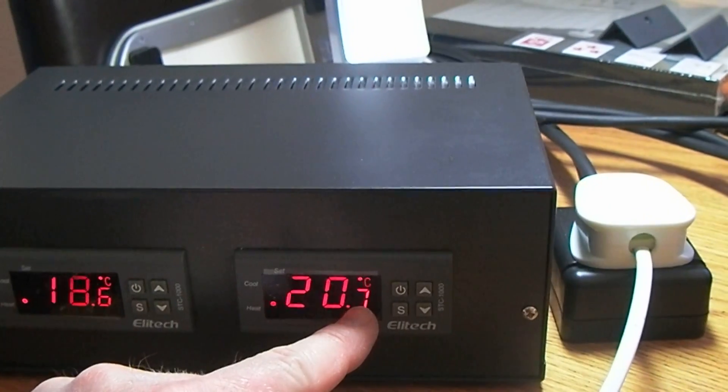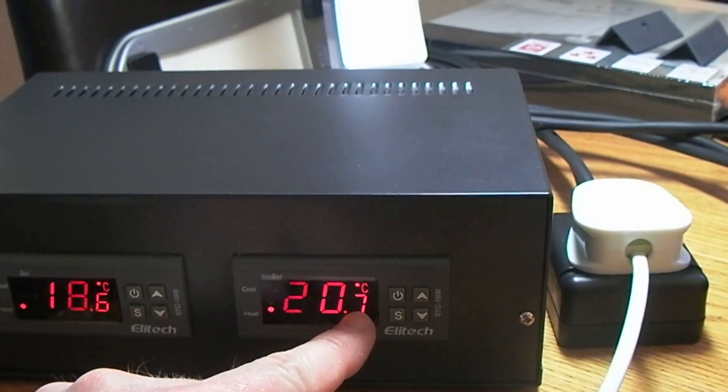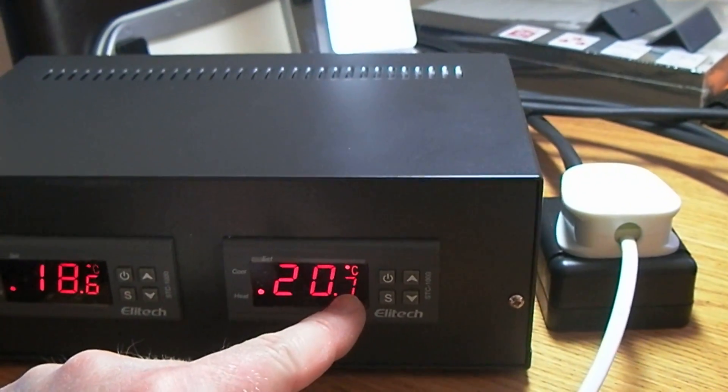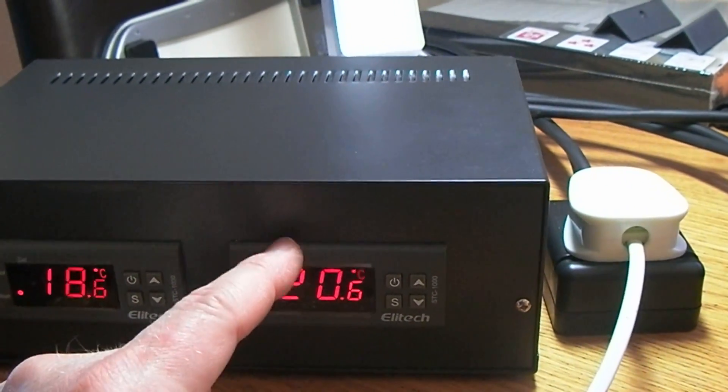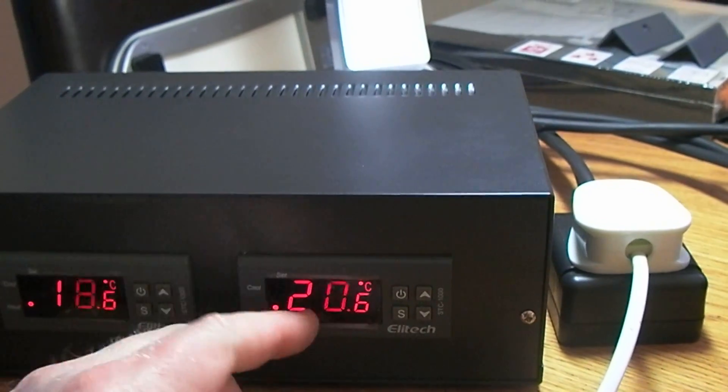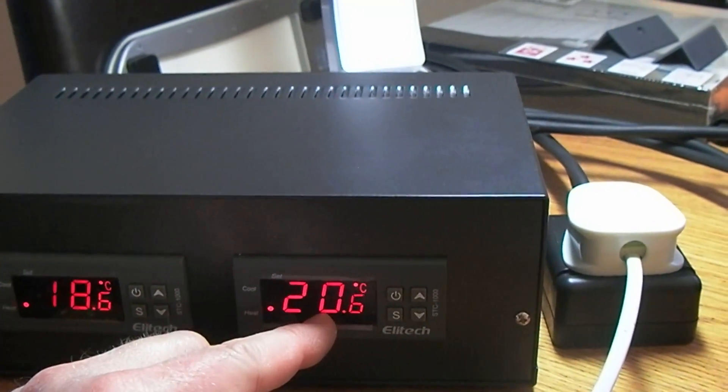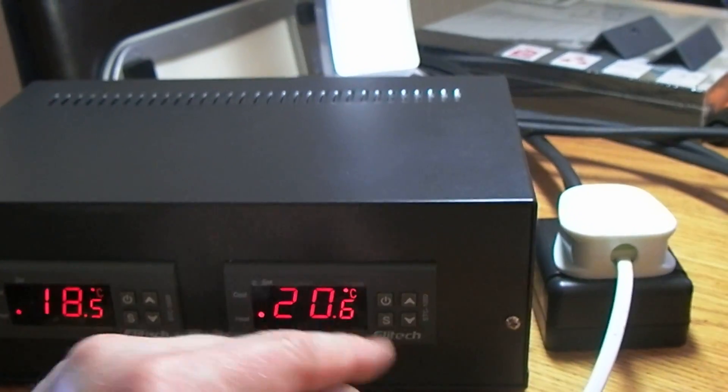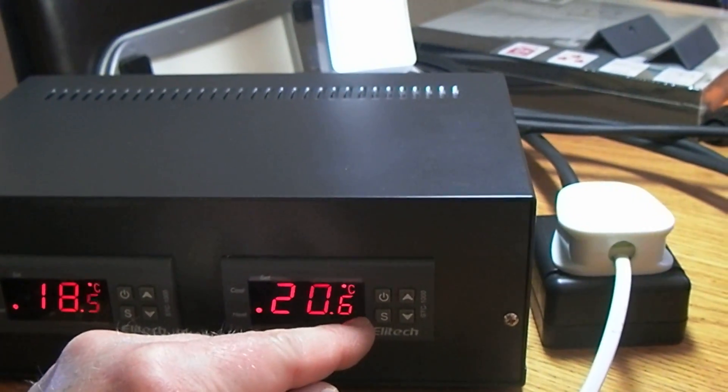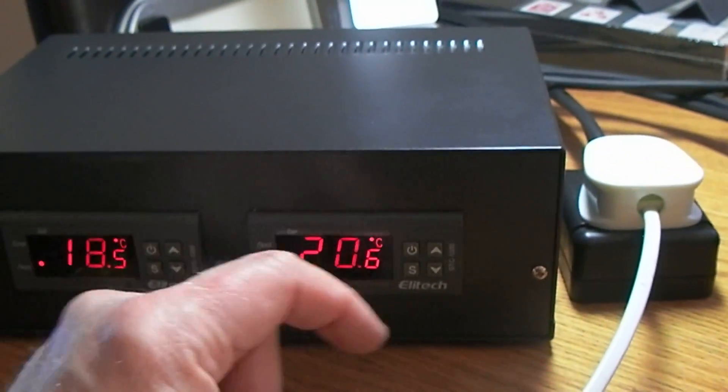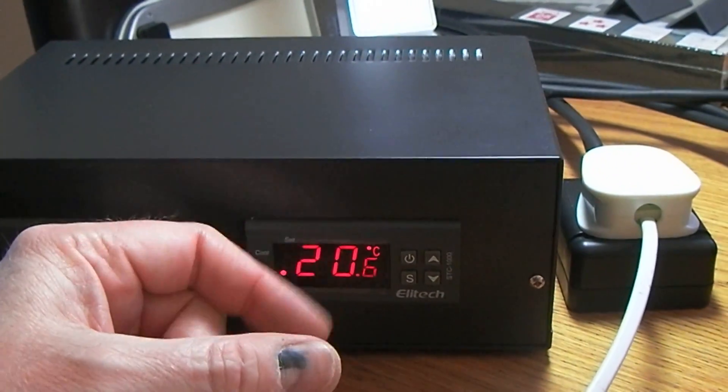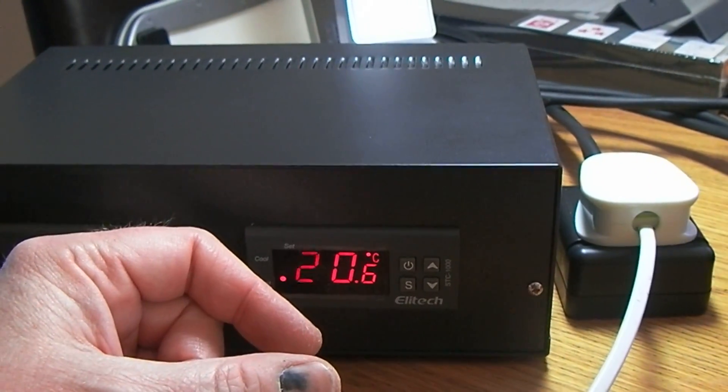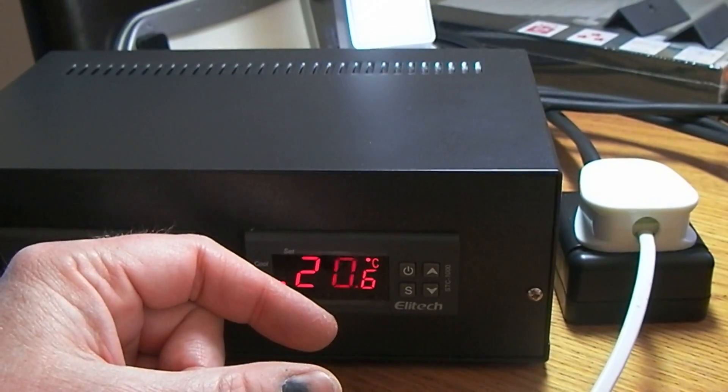So let's say the element of the heater that's being used all of the time fails, and it fails with it on. The temperature will rise, and once it gets to two degrees above the normal tank temperature, this will turn the power to the heater off.